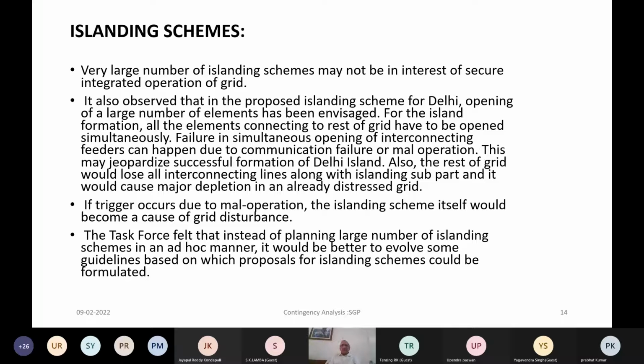So a number of islanding schemes are proposed and already are in service, but the success rate for an islanding scheme depends on many factors. For example, when the islanding scheme for Delhi was being worked out after the 2012 grid collapse, it was observed that in the proposed islanding scheme, opening of a large number of elements is required to isolate the region, because there are a number of interconnection points with the grid.